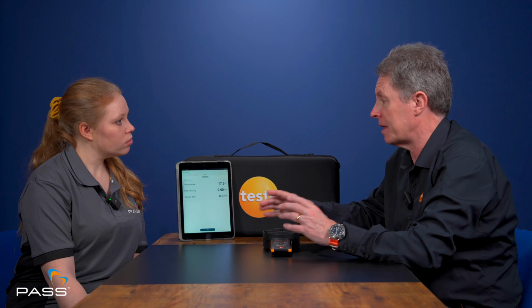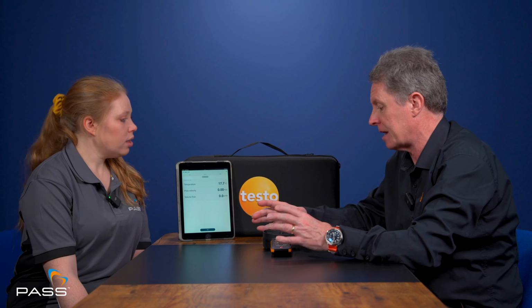So within the Part F regulations it is set down, depending on the room and its use, whether it's in a domestic building, a kitchen, a bathroom, there are predefined rates that are expected for air exchange. And it's vitally important that anybody who's commissioning a building under Part F regulations uses a vane anemometer device or an alternative device to get those measurements on the airflow, that they can then use to fill out the sign-off documents at the end, to say that the building's ventilation system has been set correctly.